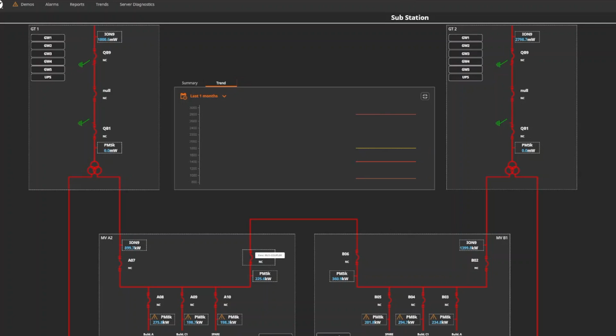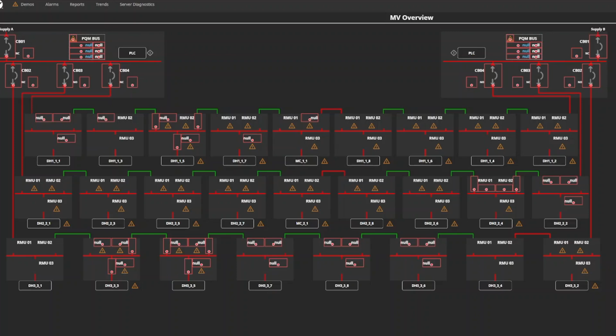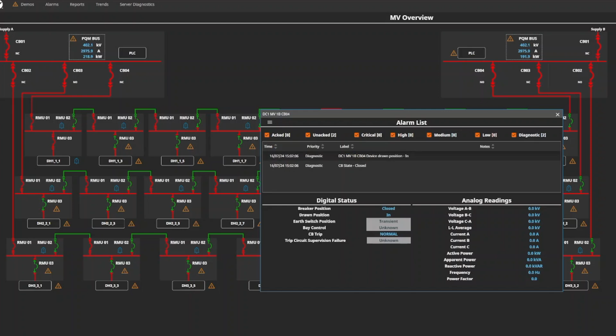Our single line diagrams are built using coordinate containers and use an SVG for each line in a diagram. With this approach, we can build out the whole diagram and then have individual control of each segment. We can then drive line animation with Ignition expressions, updating the color of the segments as data changes in real time. Leveraging Ignition's expression language, we drive the line animations and color changes in response to real-time data updates. For instance, a line might change color to indicate the flow of current, a breaker state, or an alarm condition.